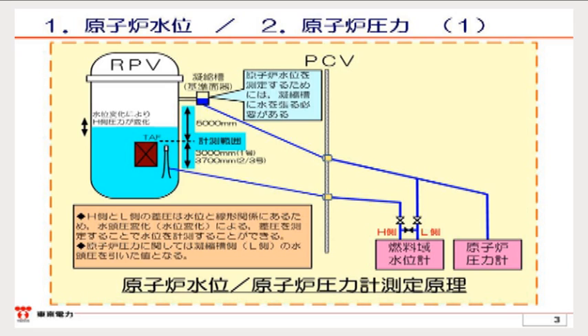Therefore, if there is not sufficient water in the condensate pot, the hydraulic head pressure, that is, the water pressure, is not measured properly, which means we cannot measure the water level properly. Please proceed to the following slide.